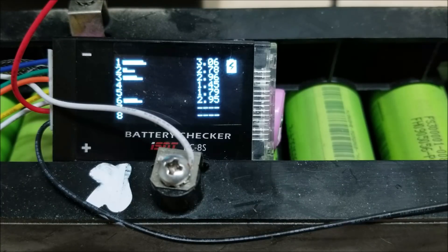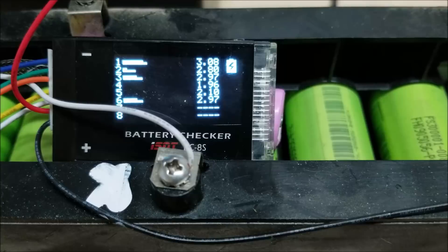Lithium iron phosphate batteries are a little bit more tolerant to heavy discharge, but it's really not good to go below two volts regularly. So this is what happens when you do a top balance and you have some weak cells. On discharge, your weakest cell will go very low. Now if this was lithium ion batteries, the cell voltage going down to zero, it's possible they wouldn't even permit you to recharge. They could catch fire on a recharge. As you can see, the voltage is slowly climbing back up, so I assume it'll probably be getting over two volts fairly soon.